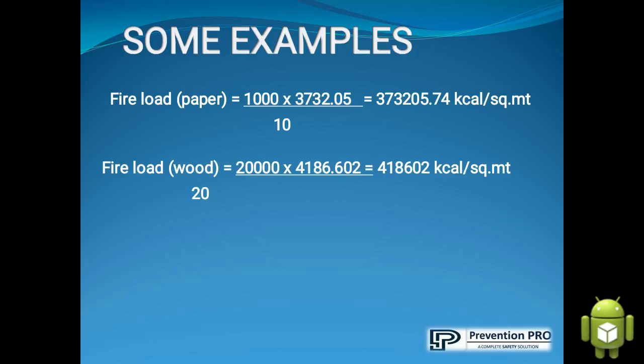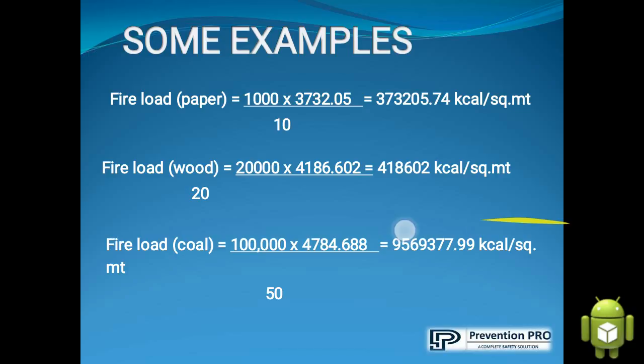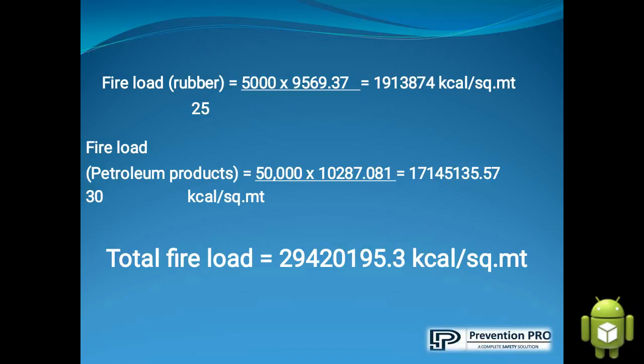Example calculation. Fire load for paper is equal to 1,000 kg of paper multiplied by 3,732.05 calorific value, divided by the area occupied by the paper, which is 10, giving a result of 373,205.74 kilocalories per square meter. And similarly for wood, coal, rubber, and petroleum product.